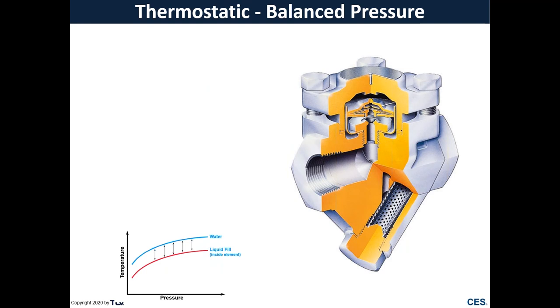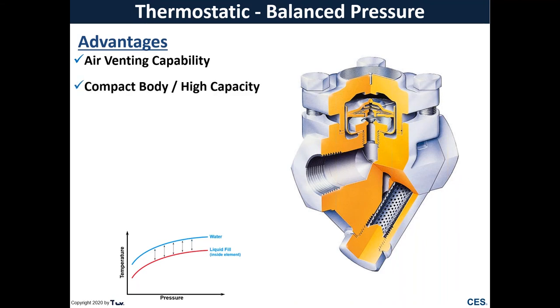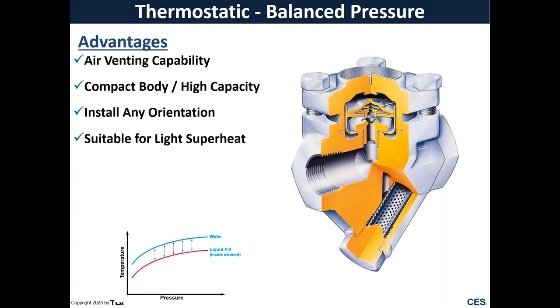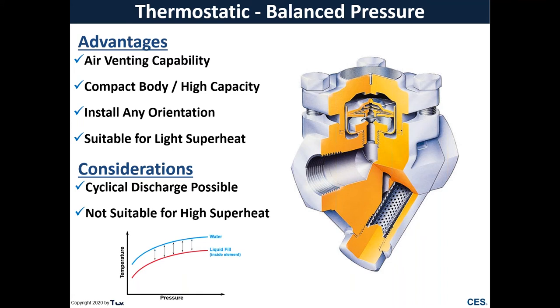So some advantages to this trap type. It's very good at venting air during startup conditions or if there's air in your system during operation. It has a very compact body and, relative to its size, a high capacity. Because this trap operates on temperature, it's not sensitive to installation orientation. And TLV's X element is actually suitable for a small degree of superheat. Some considerations when installing the steam trap: understand how it's going to operate. It's going to back up a little bit of condensate before it reopens, so there's a cyclical discharge to this trap. As well, balanced pressure traps in general are not suitable for a high degree of superheat.